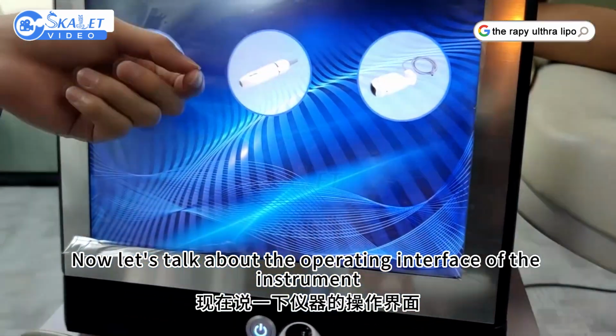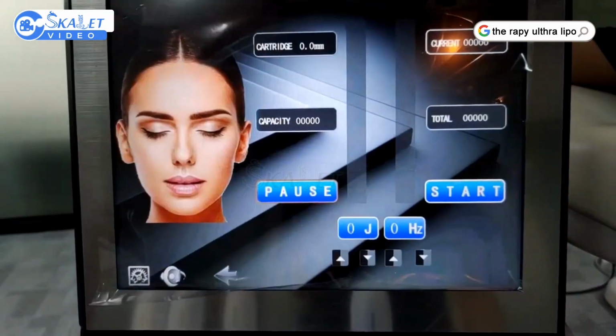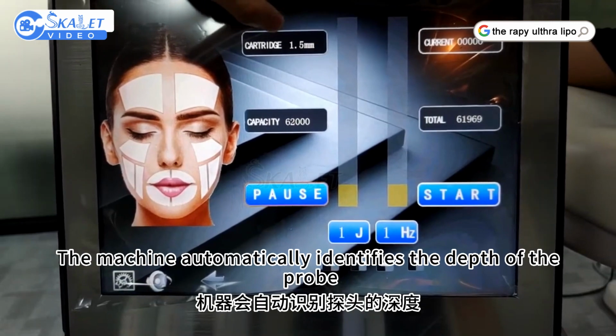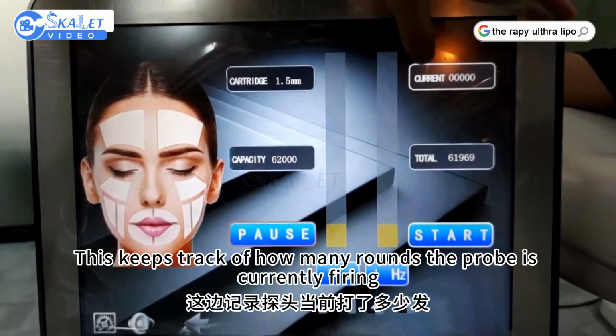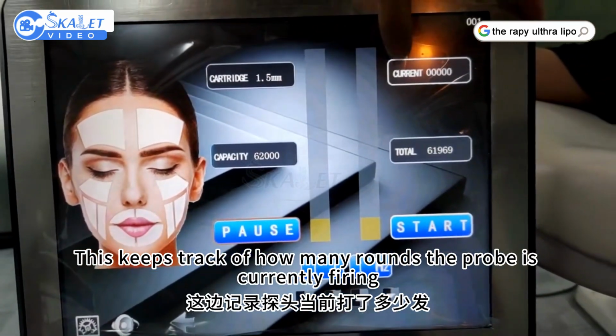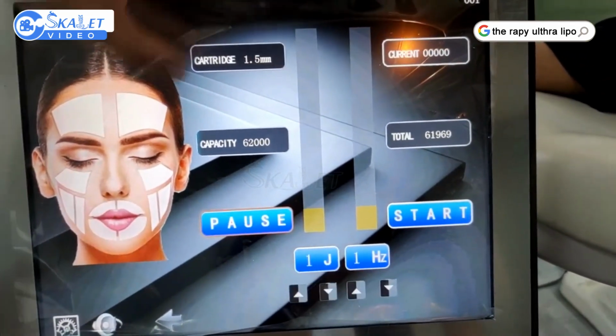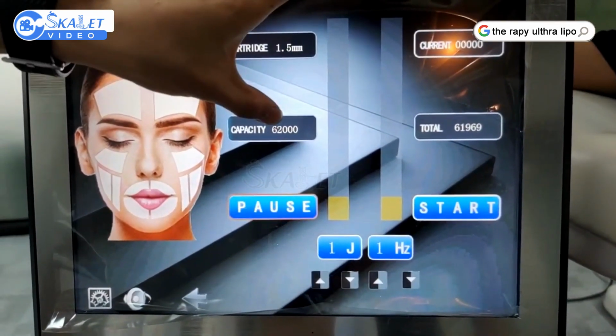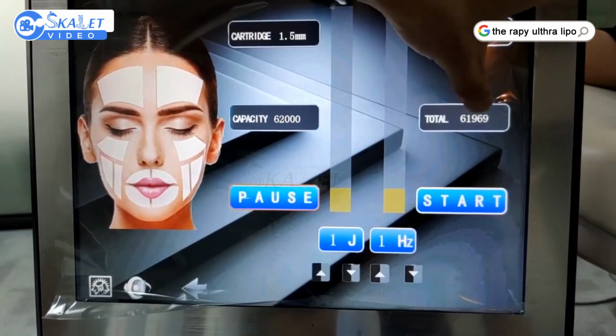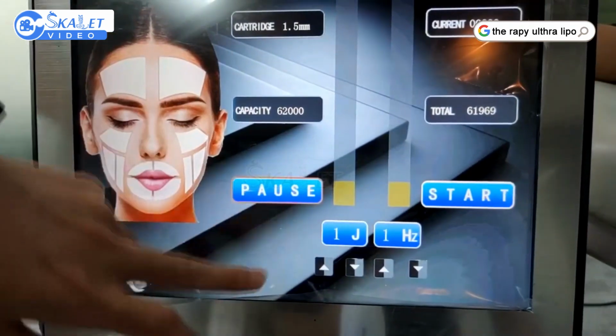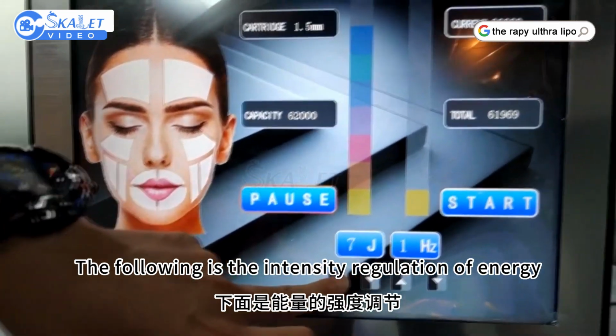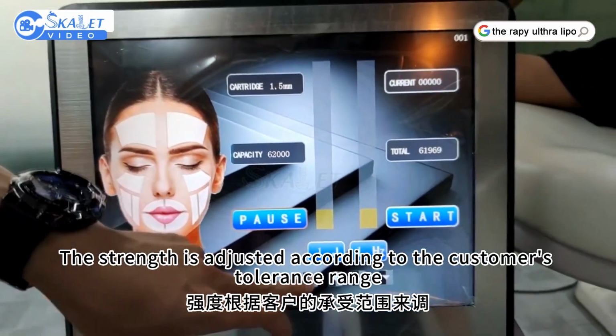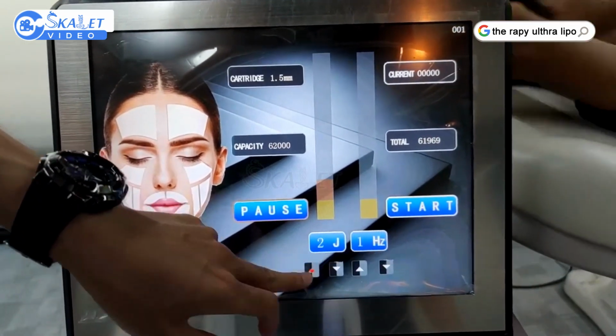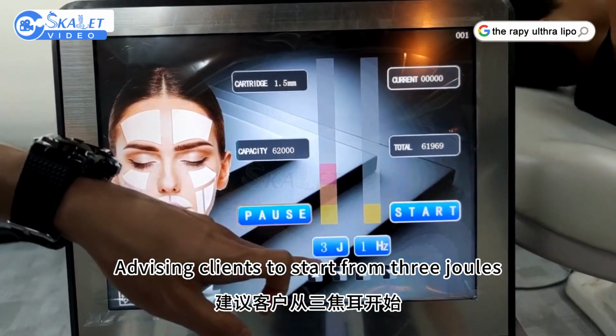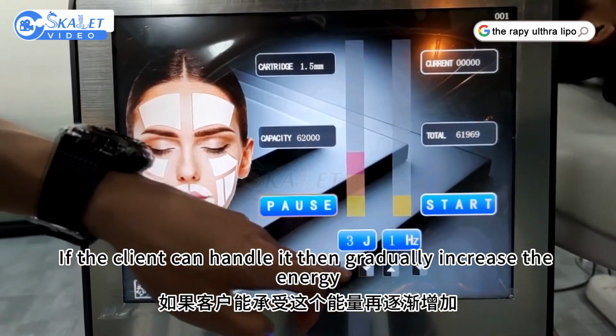Now let's talk about the operating interface of the instrument. The machine automatically identifies the depth of the probe. This keeps track of how many runs the probe is currently firing. This is the total number of probes. This is the remaining number of probes. Pause key. Start key. The following is the intensity regulation of energy. The strength is adjusted according to the customer's tolerance range. Advising clients to start from 3 joules. If the client can handle it, then gradually increase the energy.